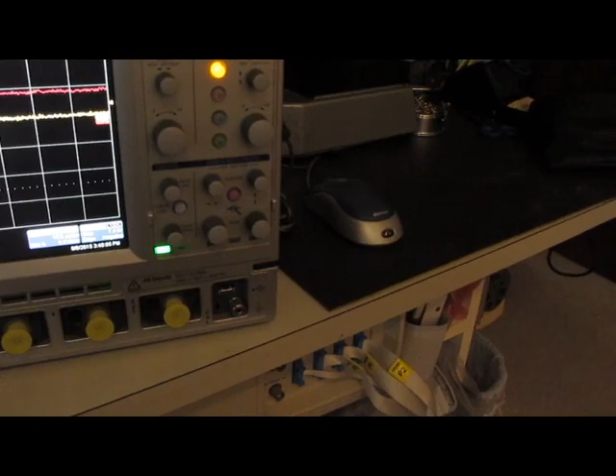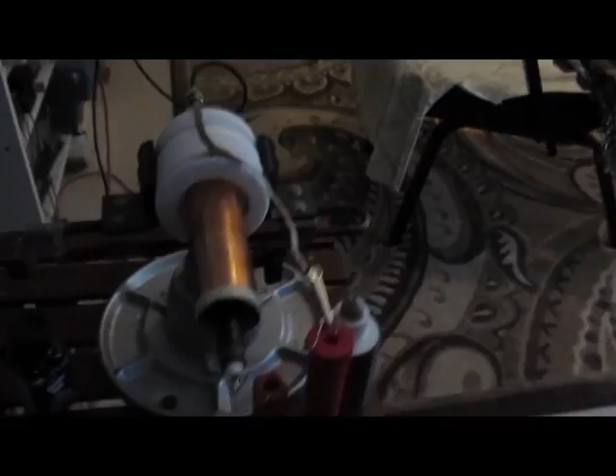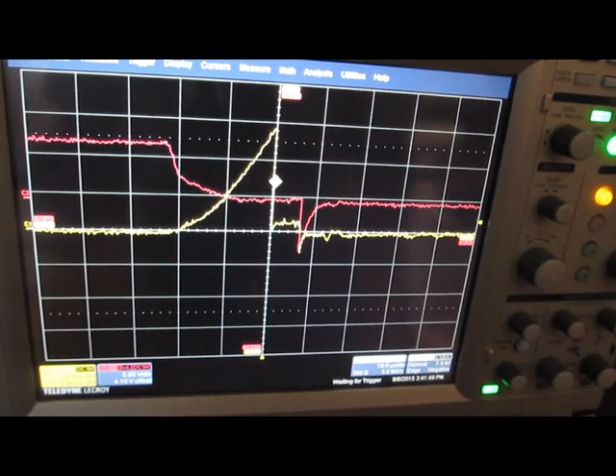Quite the arc now. We're probably 3/4 of an inch or better. And again, looking inside of the tube, everything looks pretty good. I'm not seeing any kind of problems there. And right now we are 20,000 volts per division, so you can see we're putting out about 60,000 volts. This is looking down inside of the tube here. Let's see if we can increase the gap a little bit further.